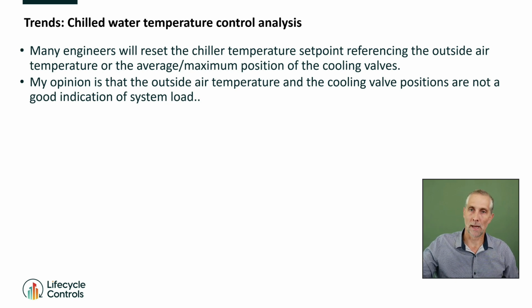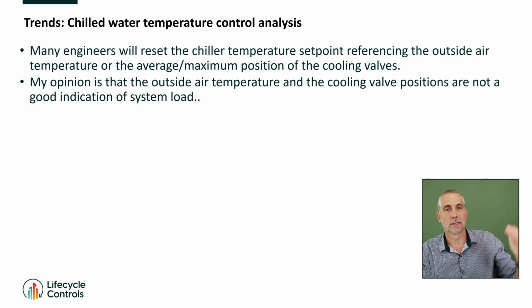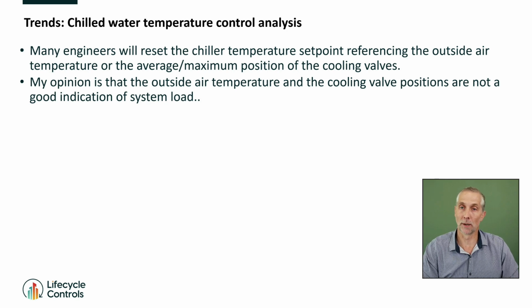And then if the AHU cooling valves are closing off, so there's less demand, so all the valves are now say 50% open, we give them a little bit less, 8 degrees Celsius of water. And if all the cooling valves are mostly closed, the average cooling valve position is say 15%, 10%, 20%, then obviously the AHUs don't require much cooling, so we raise the temperature set point up a bit more, right? So this is the idea. This is a very common control strategy in Australia, which in my opinion doesn't work. And let me explain to you why.